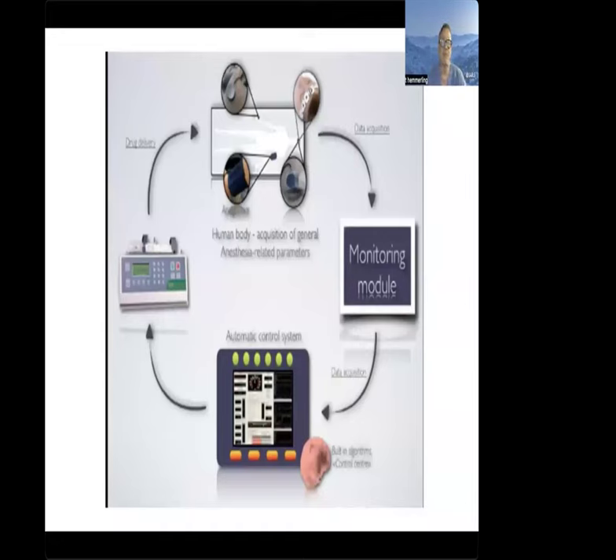Actuators, in most cases infusion pumps, manipulate the input, and the control center uses feedback from a variety of sensors. A certain target is set by the user, and the system aims to establish or maintain the measured variable as close as possible to the target value, and this over any given time.